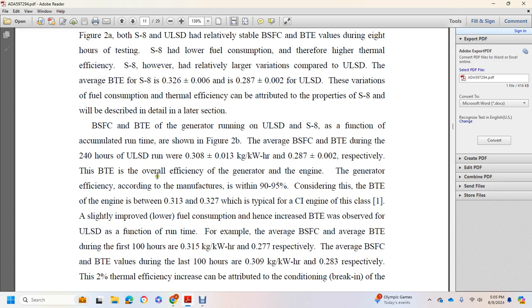For the engine generator efficiency, according to manufacturers, it is within 90 to 95%. Consider the brake thermal efficiency: the engine is about 0.313 and 0.327, typical for a compression ignition engine of this class, slightly improved with lower fuel consumption. Hence, the increased brake thermal efficiency was observed with the ultra-low sulfur diesel as a function of the runtime. For example, the average brake-specific fuel consumption and brake thermal efficiency during the first 100 hours were 0.315 kg/kW-hr and 0.277 respectively.